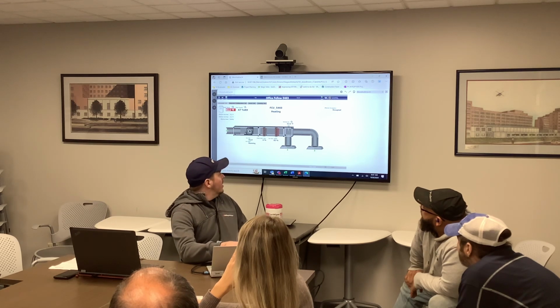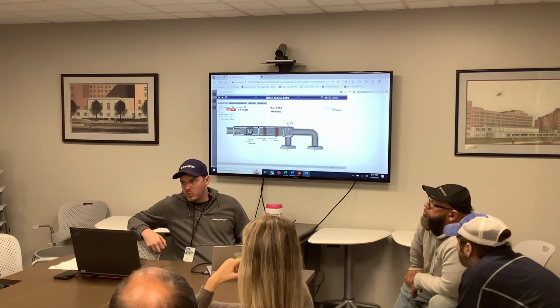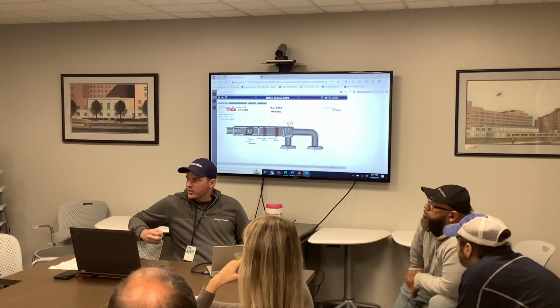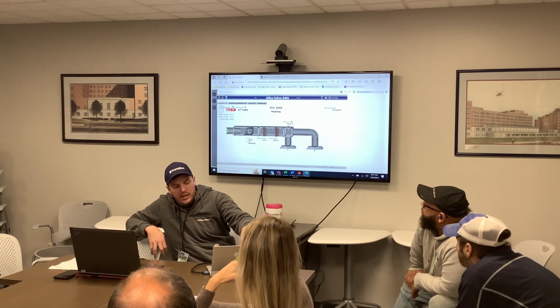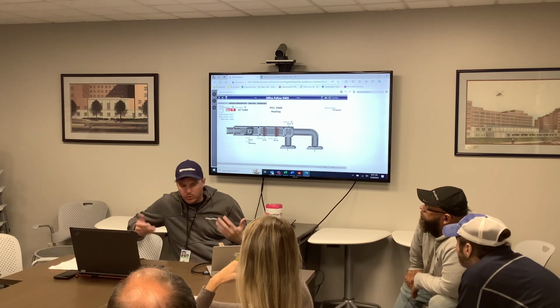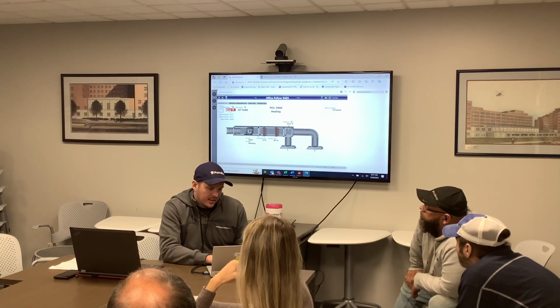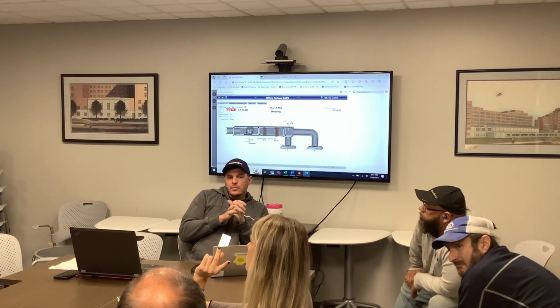at. So the hot water here is not piped into our new heat exchanger in our hot water, it's piped into your dual temp. And as of right now, we have no sequencer operation to actually monitor what's in that dual temp. So this system, as it's programmed right now, thinks there's hot water in there when it's really chilled water. So it's obviously just gonna open the hot water, flooding with chill, and it's gonna overcool the space, which is what we're seeing. So we're not having reheats when we need them, if it's during chilled water season.